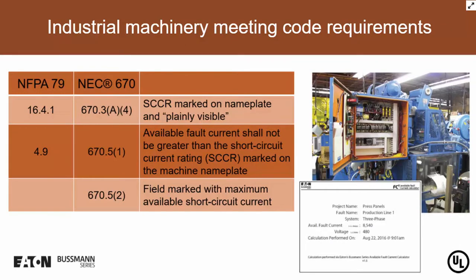Now here in this particular slide, we're showing a couple of requirements from NFPA 79 and NEC Article 670, where we've got a little bit of a comparison. First, we're going to talk about the nameplate required for industrial machinery. And the nameplate requirements in NFPA 79 are covered in Chapter 16, specifically paragraph 16.4.1. We have similar nameplate requirements for machinery in Article 670, 670.3(A)(4), that's the section. They're quite similar, except you will see that the NEC only deals with the electrical parameters. It does not get into specifics like the manufacturer's name or trademark or serial number or that kind of information. That's typically covered in a product standard, like, for example, the standard that UL uses for industrial control panels, 508A. So if you take out that information, basically the two documents are covering nameplate information quite similarly.